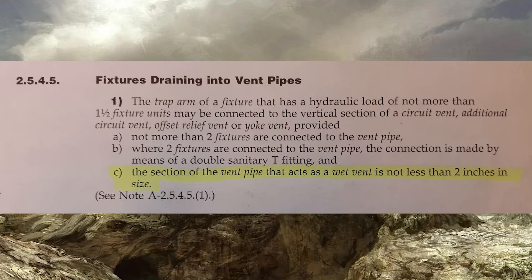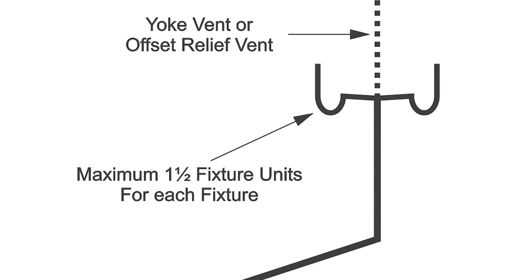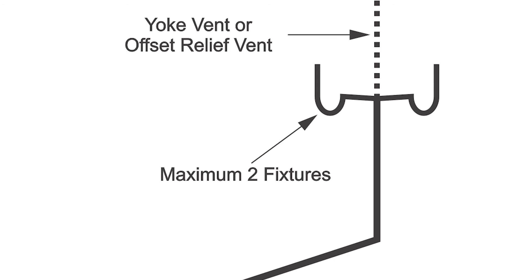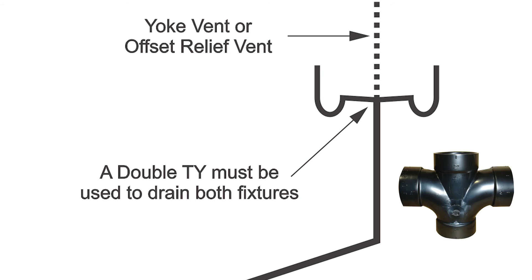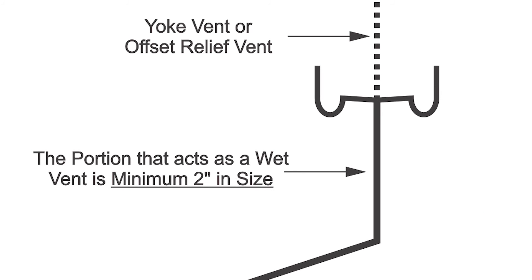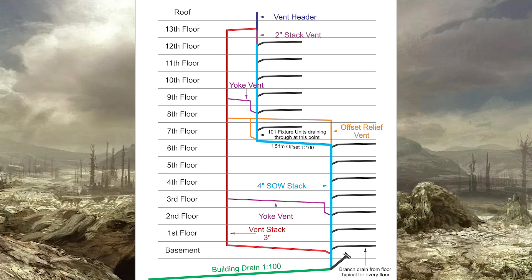Much like circuit vents, additional circuit vents, and yoke vents, we're allowed to put fixtures into an offset relief vent. Same clause 2545. The key points: fixtures are maximum 1.5 fixture units each, a maximum of two fixtures can be connected, and where there are two they are connected by means of a double TY, and the drain that drops down from them needs to be minimum two inch. Thank you for watching — stay tuned for the next video on sizing requirements for offset relief vents. Until then, have a great day.